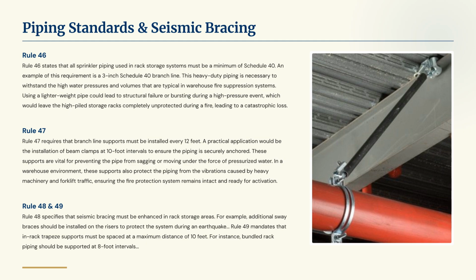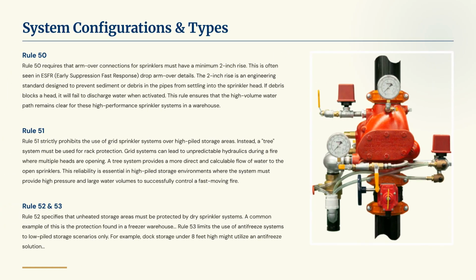Rules 48 and 49 cover enhanced seismic bracing and the maximum spacing for in-rack trapeze supports. Rule 50 requires a minimum 2-inch rise for arm-over connections to prevent debris buildup. Rule 51 prohibits grid systems over high-piled storage, mandating a quote tree system. Rules 52 and 53 cover the use of dry and antifreeze sprinkler systems.